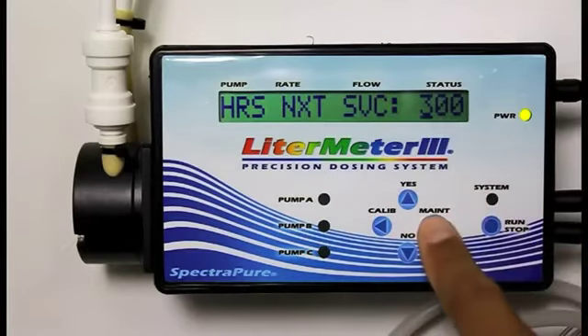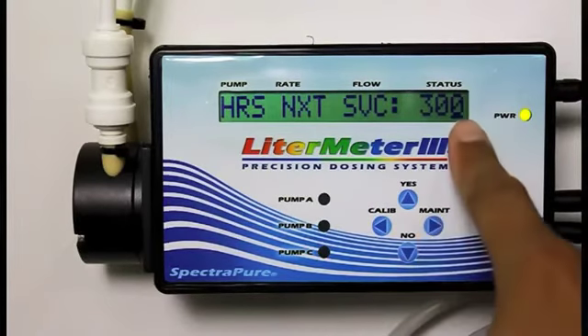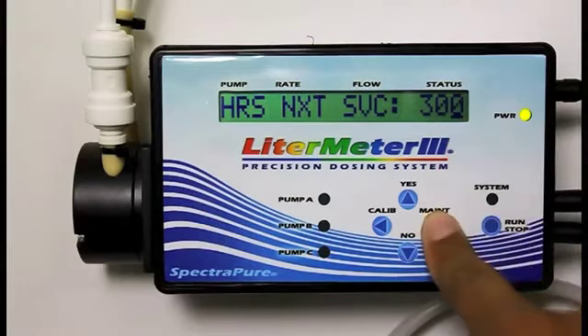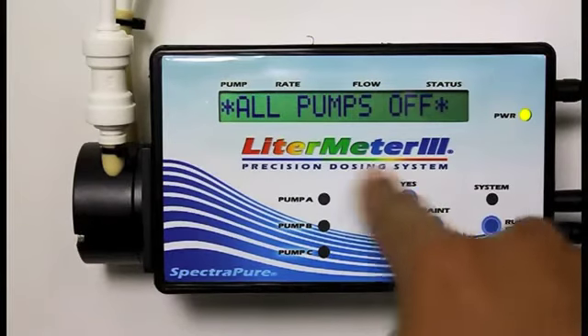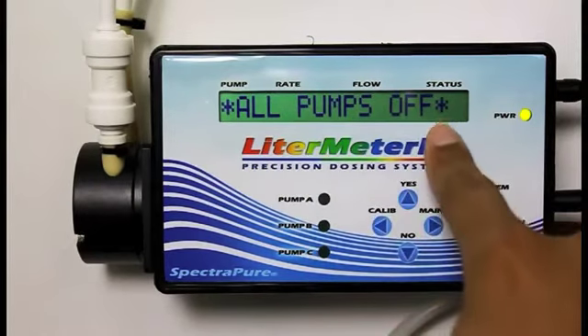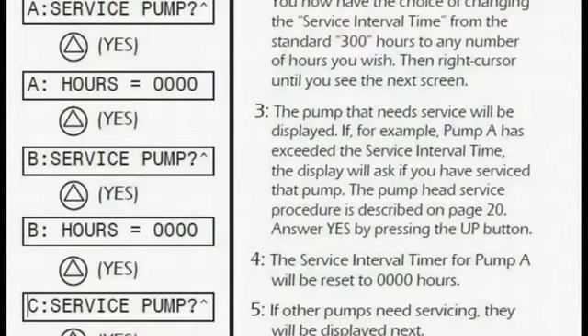If we continue to move the cursor to the right, as we get to the last digit, pressing once more will reveal any pumps that need service. If there aren't any, the LiterMeter just returns to all pumps off. When a pump's accumulated on time exceeds the service interval, the LiterMeter beeps once per minute and flashes a message on the display until the pump is inspected or serviced or the timer is reset. Refer to page 13 of our manual for additional instructions on how to reset the timer. But for now, our pumps are all set up and good to go.